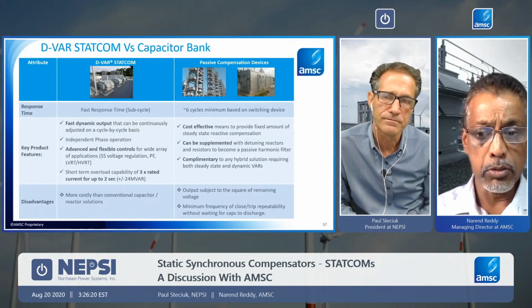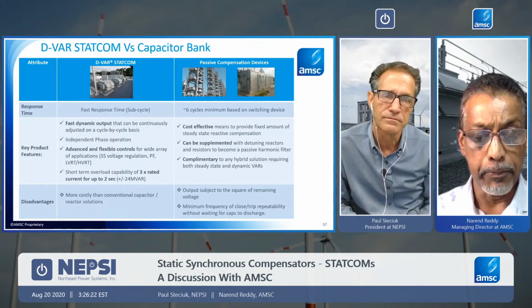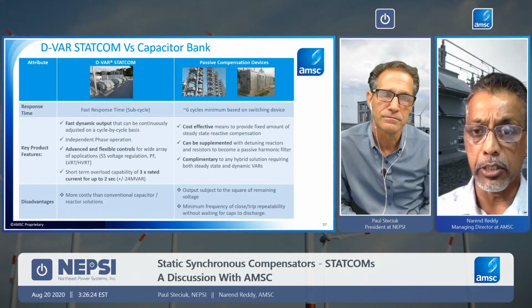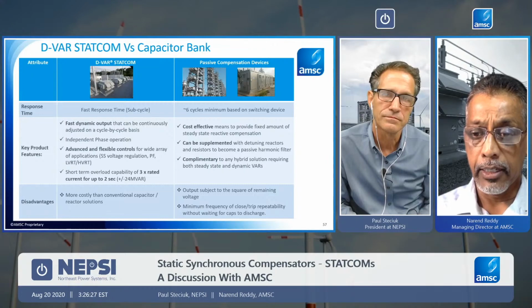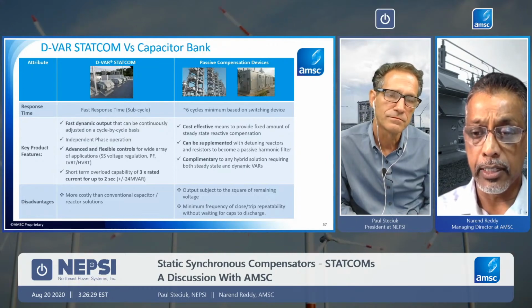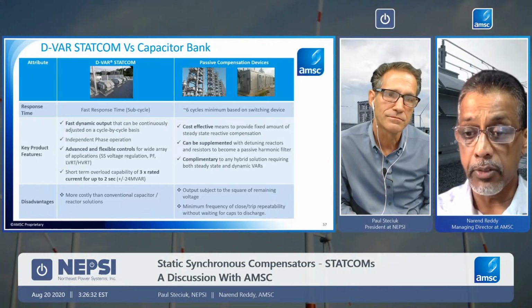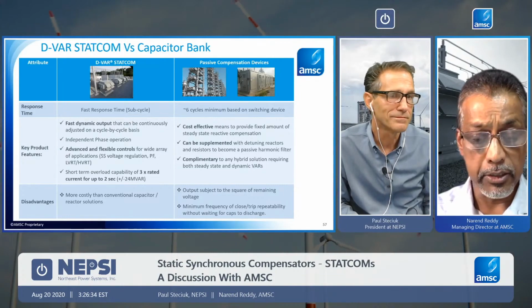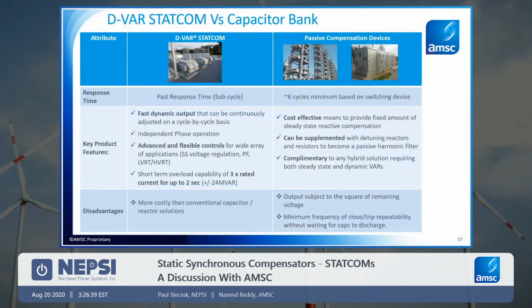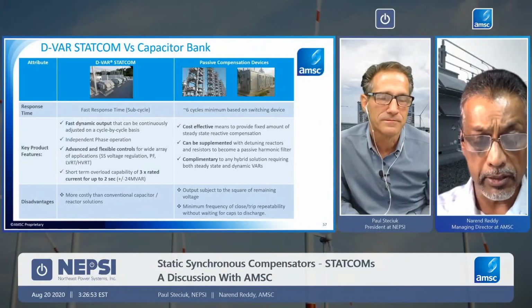So I always go back to what the application is. If we understand the application and know what the customer wants addressed and solved, and obviously there'll be a budget that needs to be met, all those things have to be managed. If it's a dynamic problem, as we discussed, like flicker mitigation or low voltage ride through, high voltage ride through, then obviously a capacitor bank or a passive device will not be able to solve that problem.